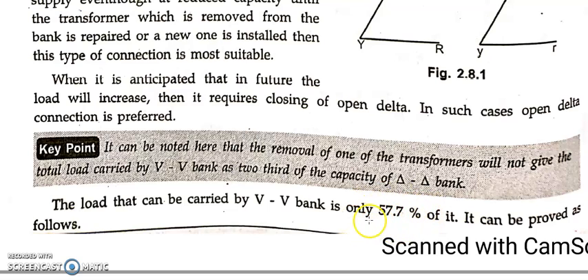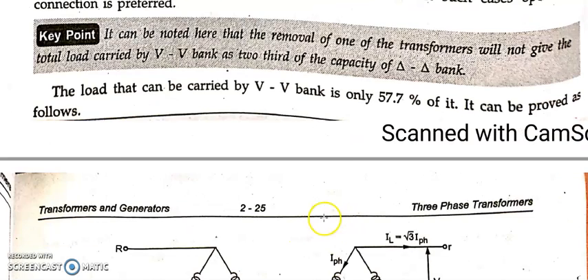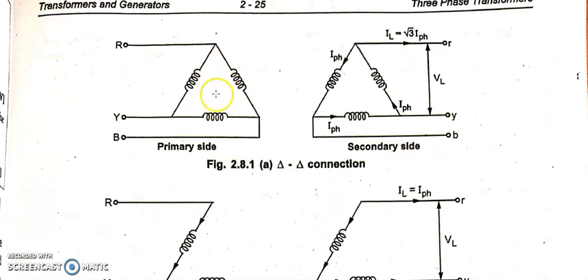You may get the question, why is the load for a VV bank only 57.7% of the total kVA of the transformers? It can be proved as follows. Let us take a normal healthy delta-delta connection. You can see this is the primary side and this is the secondary side. Like I told you, whatever current flows here is the line current, and whatever current flows in the delta part is called delta current or phase current. Delta current, phase current and line current are not the same, as the current gets divided here. So I phase equals IL by root 3, or IL equals root 3 into I phase, whichever you call it, both are the same. But here line voltage and phase voltage are both the same.